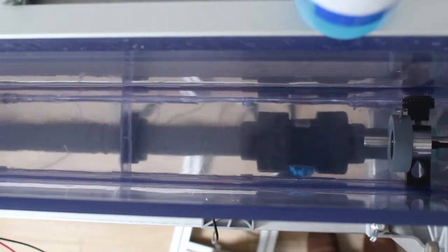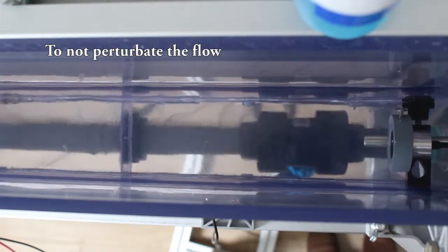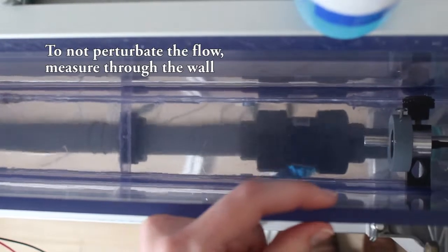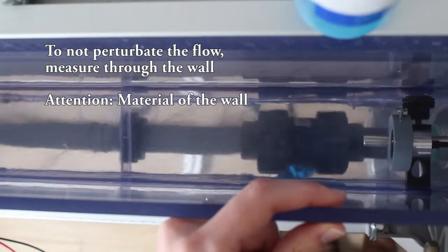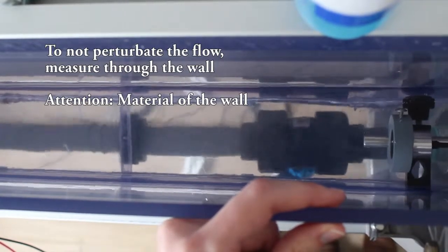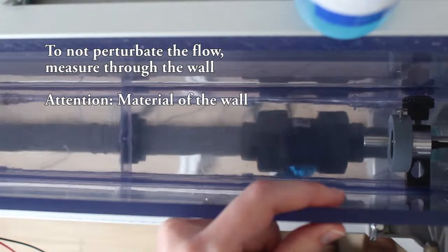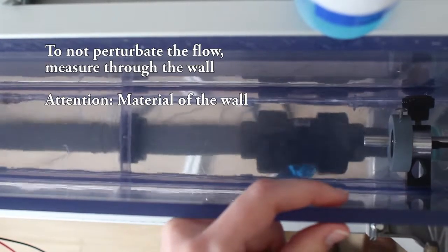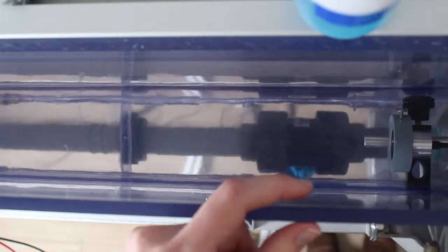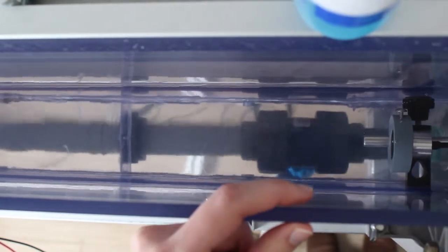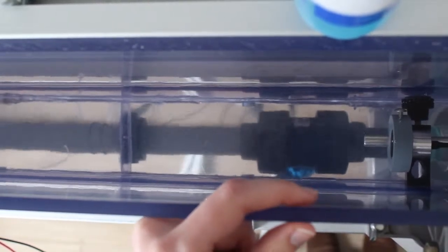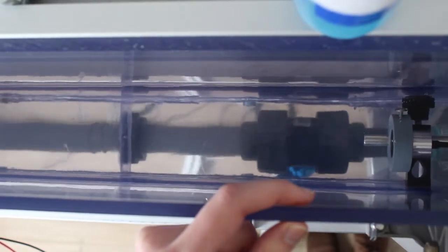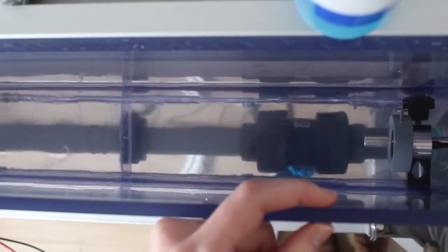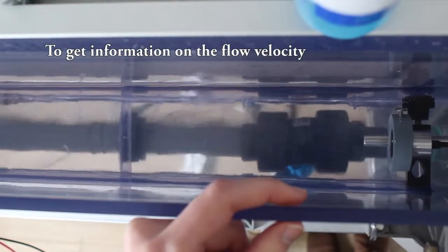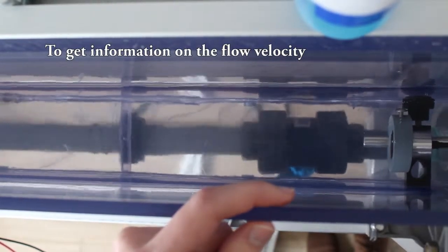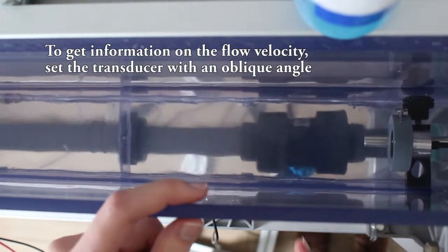If one does not want to perturbate the flow at all, it is possible to measure through the wall. The material of the wall is of great importance. The acoustic impedance of this material could hinder the acoustic pulse to reach the liquid. Plastic walls work fine. Here we have a PVC wall, for example. As the measured velocity is the projection on the transducer axis, if you want to get information on the flow velocity, you will have to set the transducer with an oblique angle.